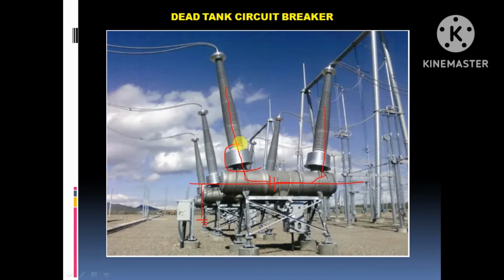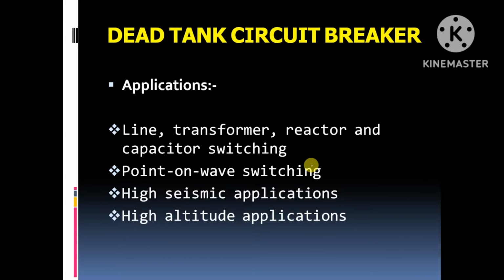And this is called the bushing CT. In the incomer side or outgoing side it is installed, where it is utilized for protection and metering. This bushing CT is utilized for metering and protections. The dead tank also has some advantages, like it is utilized for line, transformer, reactors and capacitor switching. It is a point of on wave switching also, and for high seismic applications, where a location is more prone to earthquakes, in those cases that type of circuit breakers are suitable.